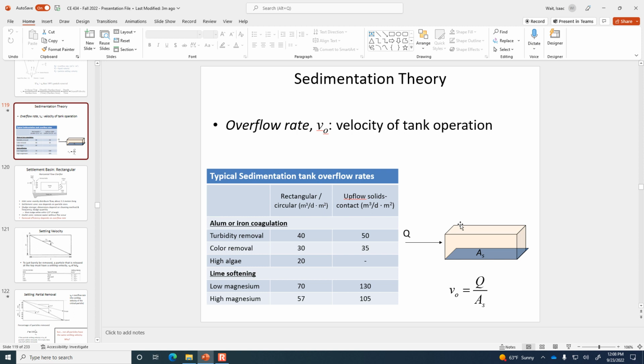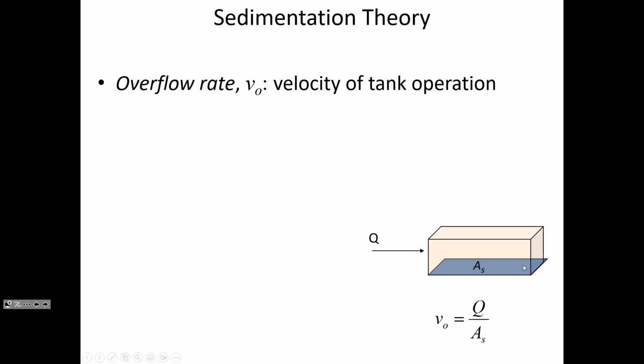So kind of interestingly, this isn't something that I talked about last time, the loading rate is independent of how tall the tank is. Like you could have a 1 meter tall tank or a 2 meter tall tank or a 3 meter tall tank, and this overflow rate, which is just an indicator of how heavily you're loading solids into the settling basin, stays the same. It's independent of how deep the water is.